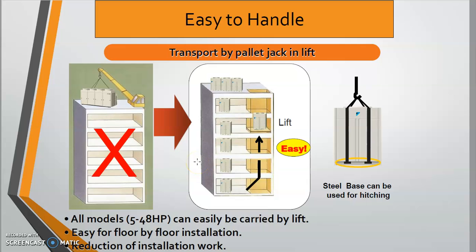So this is another advantage of using VRV system compared to centralized system. As you can see on the left hand side picture here, if we are installing our cooling tower or chiller system, we need of course a crane because it is quite and very heavy, because the lift cannot fit the cooling tower and the chiller.